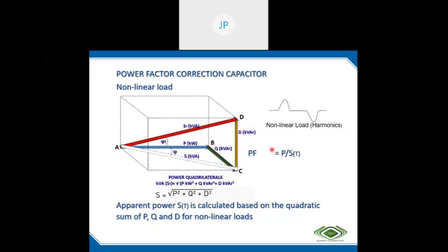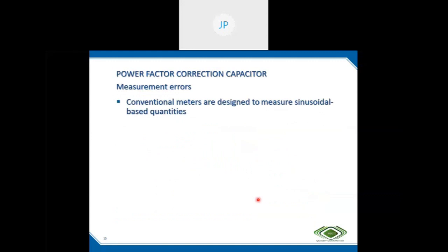So the power factor is P by ST, and one influencing factor is the displacement power factor, which is equal to cos phi. The other is the distortion power factor, which is equal to 1 divided by the root of 1 plus THD squared. THD decides the distortion power factor, cos phi decides the displacement power factor, and the net power factor will be the product of the displacement power factor and the distortion power factor. So actually all the measurements should be true parameters.